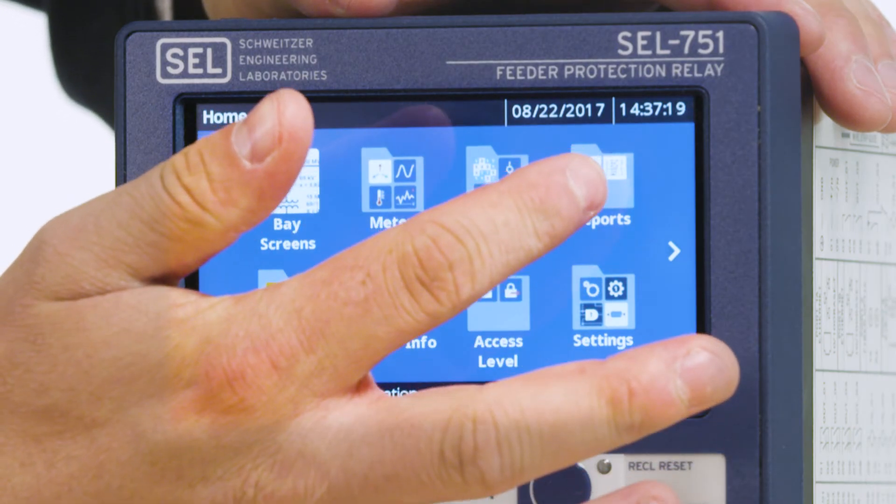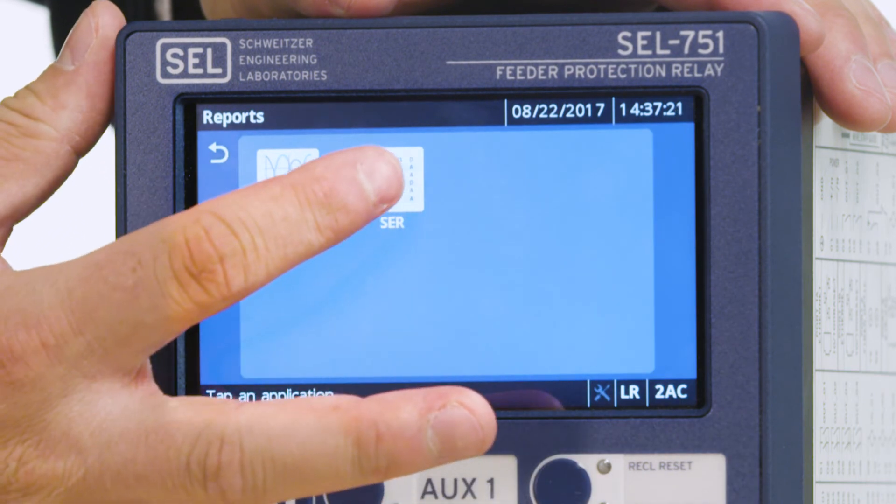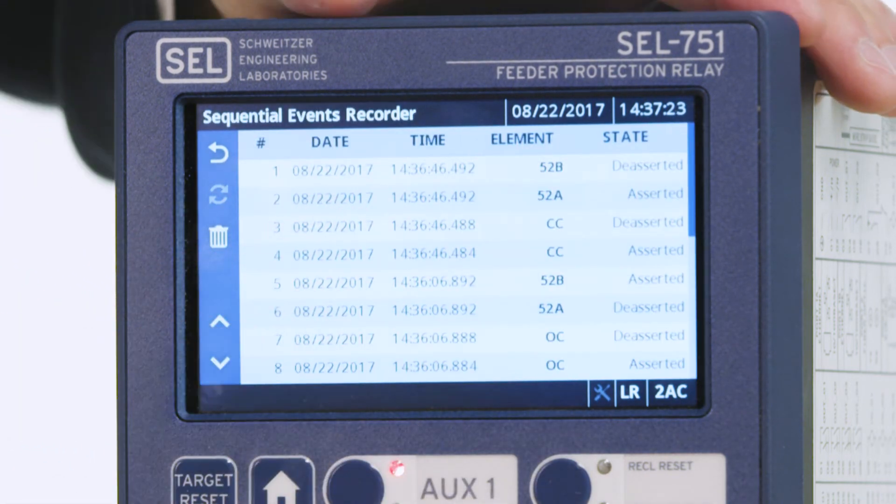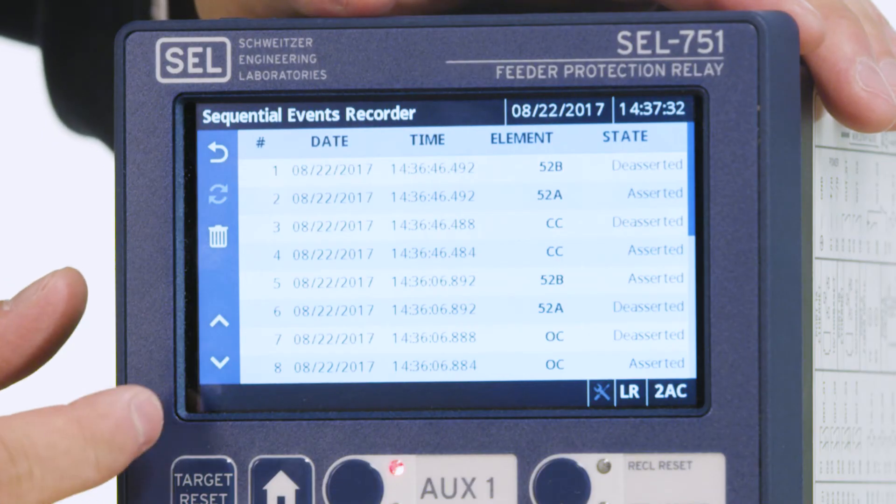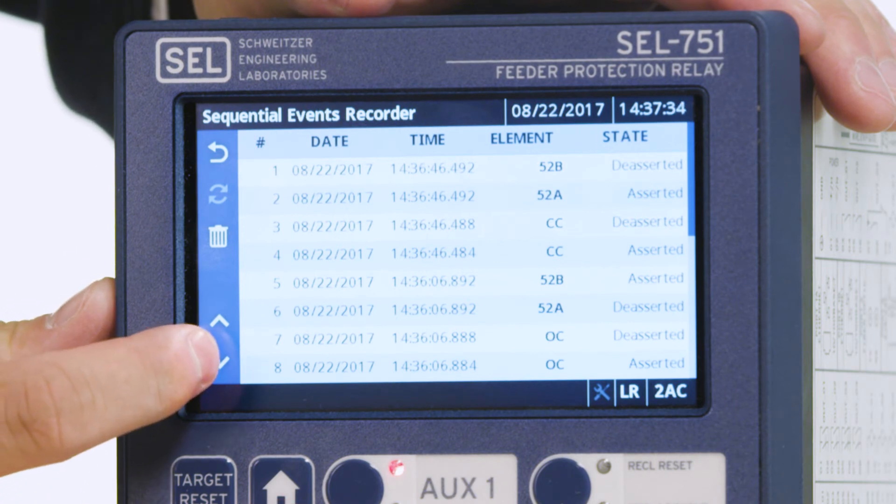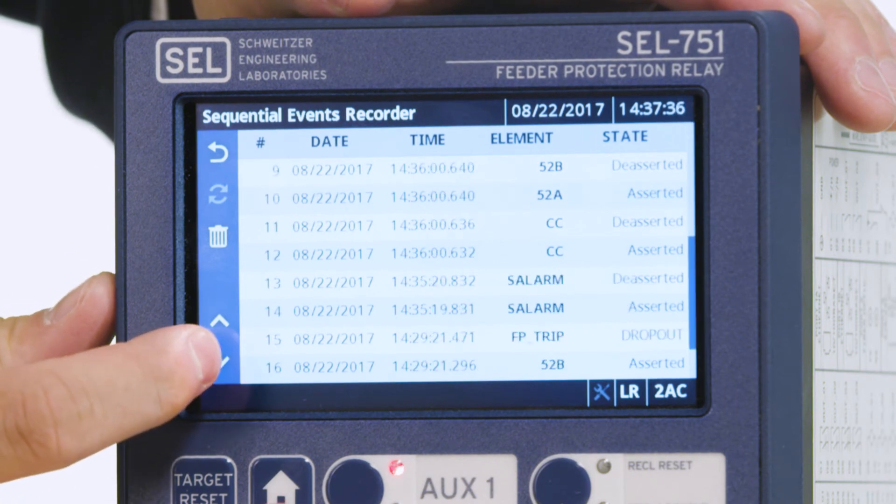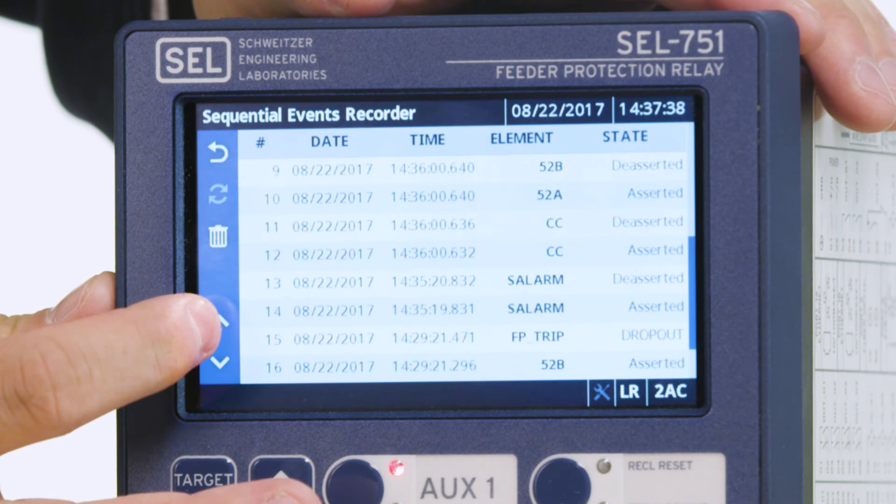Next, we are going to look at the SER application or the sequential event recorder. In the SER, you can log up to 1024 items. These items can be customized by the user. As you can see, we can scroll through the various SER log items.